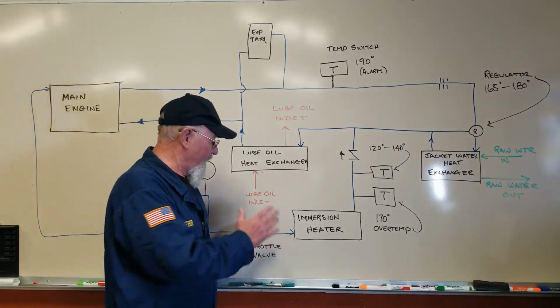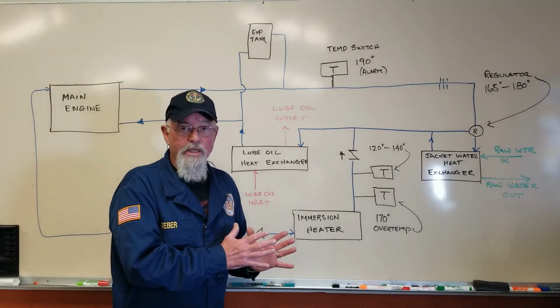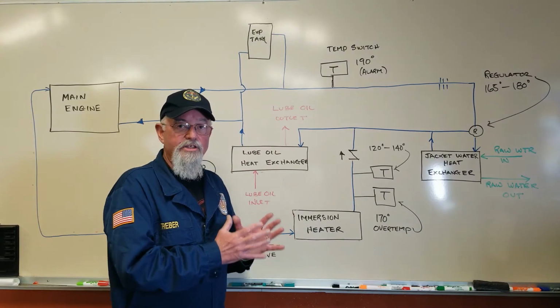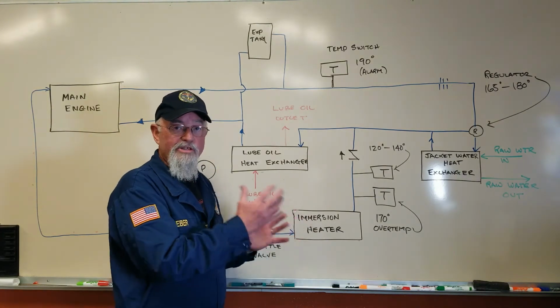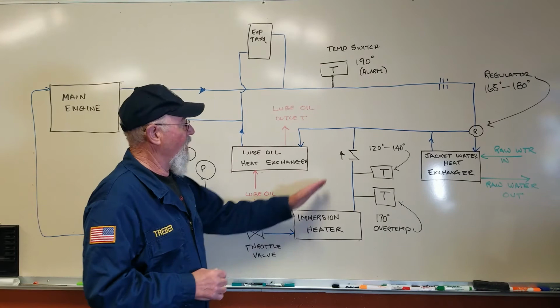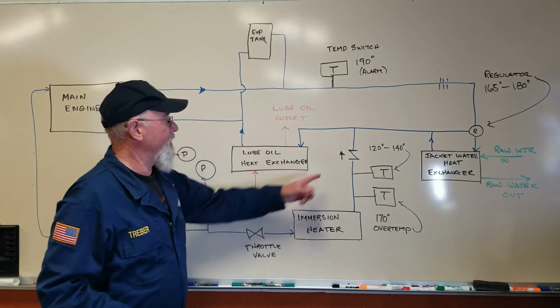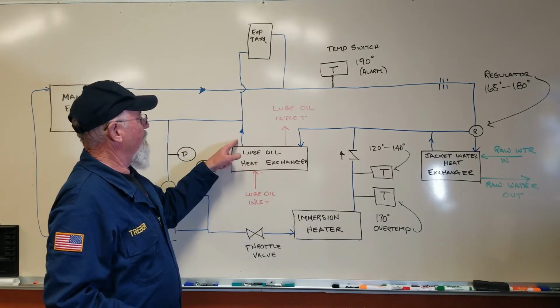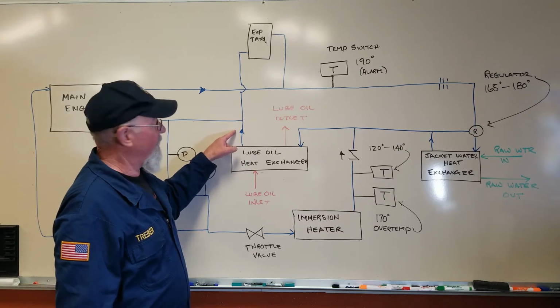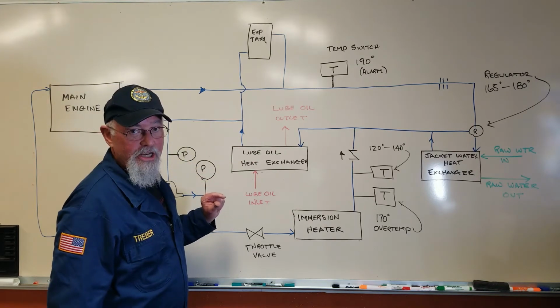So what we're doing is we're heating water because it's easier to heat water, and it's easier and faster to pump the water because it's a non-viscous liquid. So through the heat exchanger, the jacket water goes. Then it comes out of the lube oil heat exchanger, I should say.